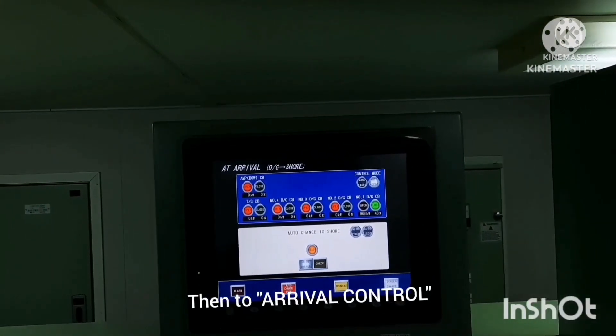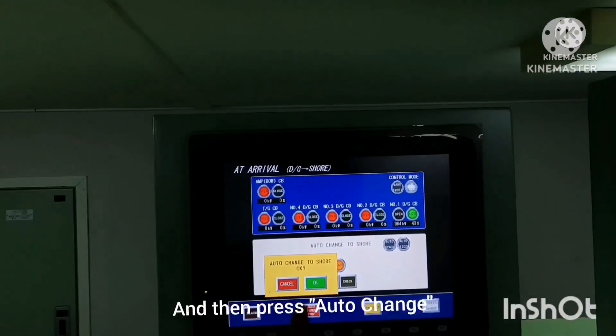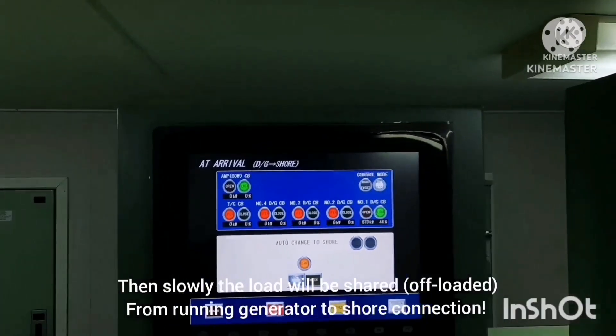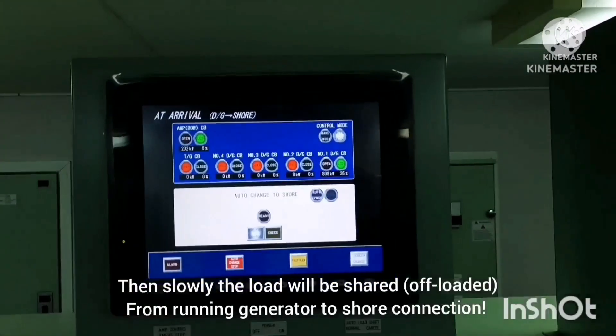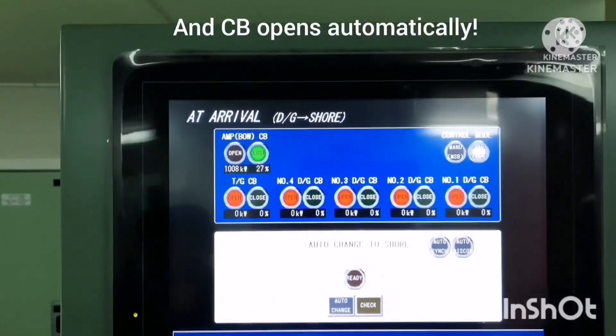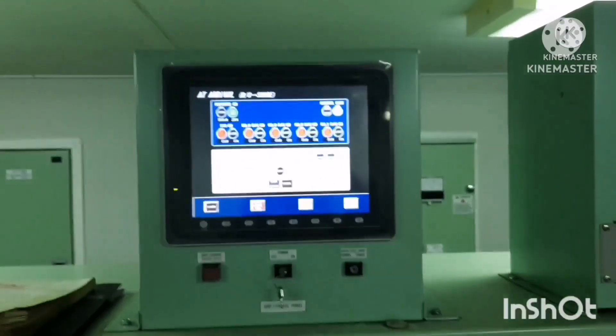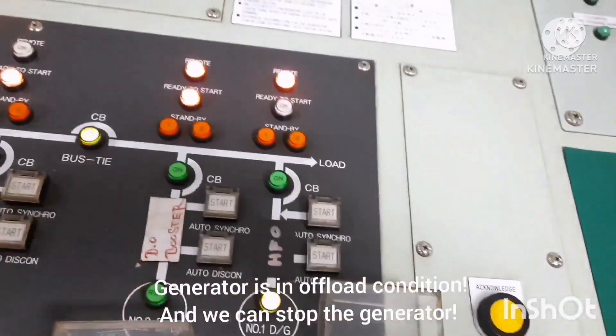Go to arrival control mode and press auto changeover. You will see a prompt asking whether you want to change over to shore — press 'OK'. Once OK is pressed, you can see the load slowly changing over from ship to shore connection. The load is getting transferred and the circuit breaker opens automatically. Now the ship is on shore power. You can see the generator is in offload condition, and now we can stop the generator.